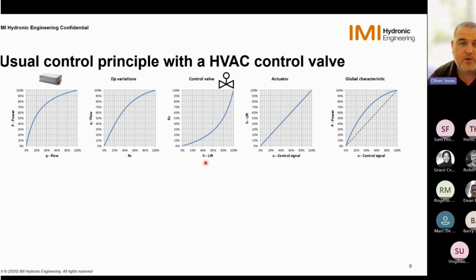So if we look at the different characteristics for a typical system, we have a terminal unit characteristic, which is non-linear. So unlike the actuator that's shown here, which is a linear characteristic, the terminal unit characteristic is non-linear due to the physics of its exchange. Then we have a control valve with an equal percentage control with a nice Kv characteristic according to an inverse shape of the terminal unit characteristic. If we compensate this non-linearity by this one, and we then select an actuator that works essentially in a linear way, the difficulty we have is the dP variations. So the hydronic network is introducing dP variations into the system, which make the flow curve that we would like to get to manipulate the terminal unit look different to the one that we've chosen.